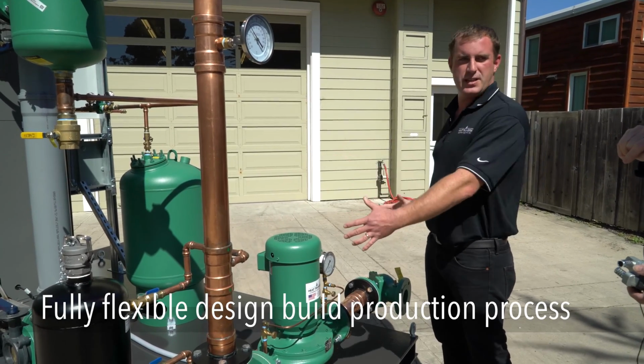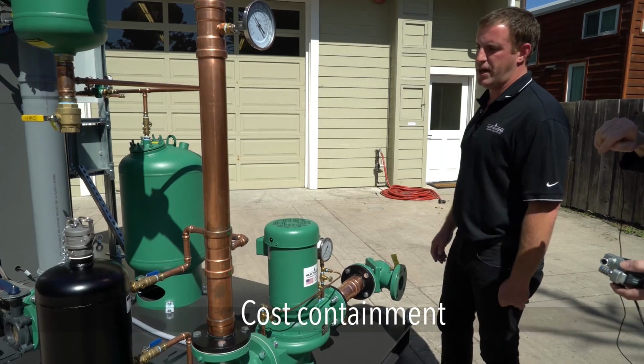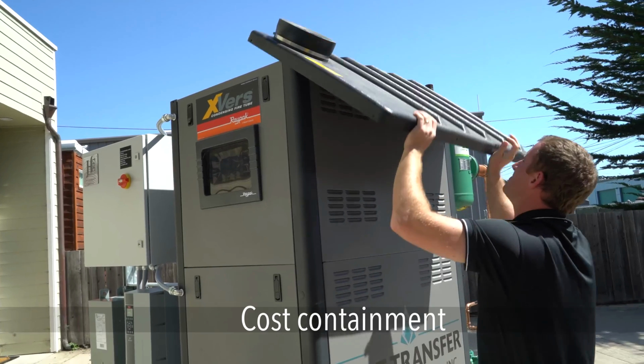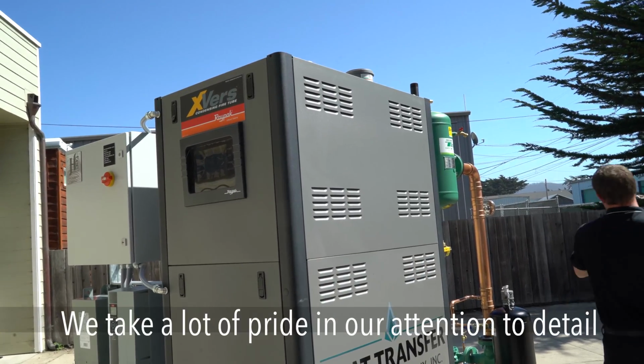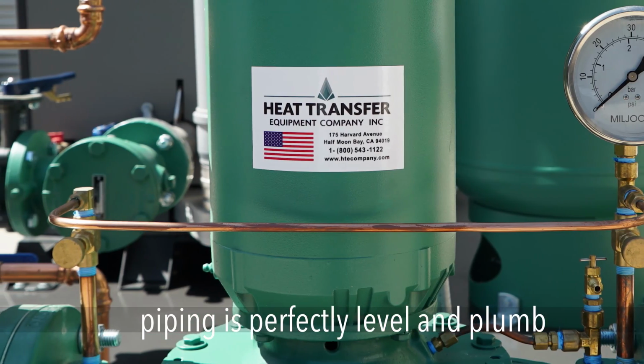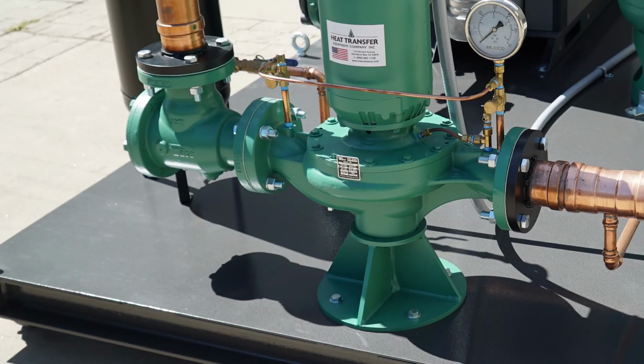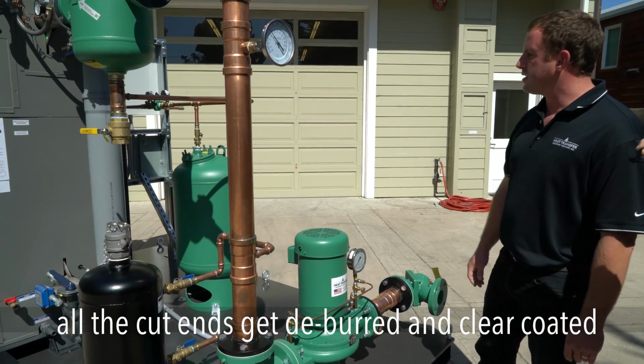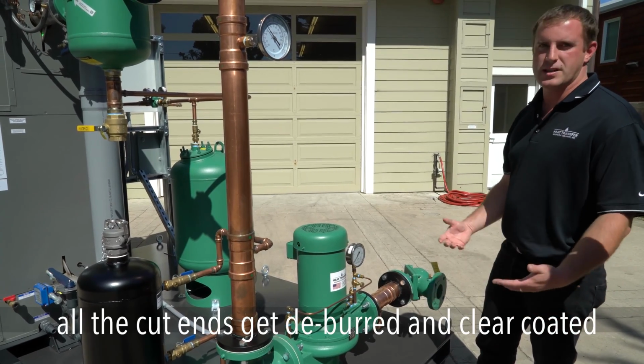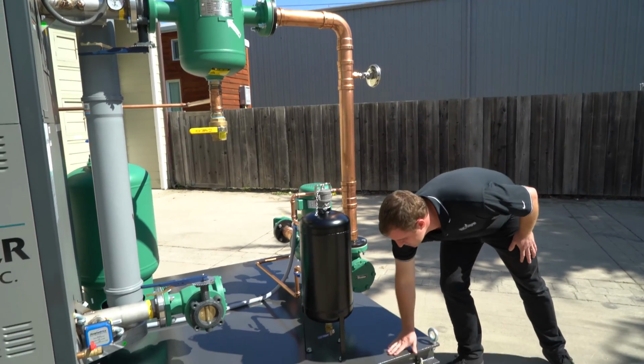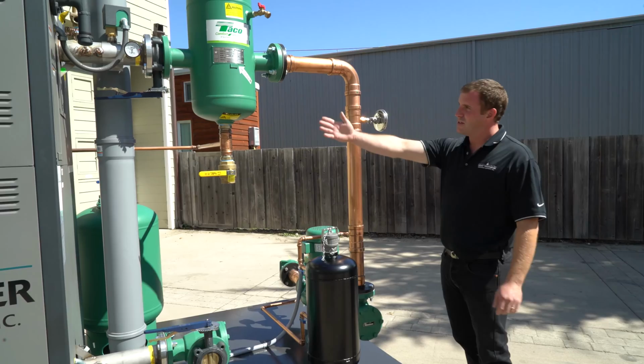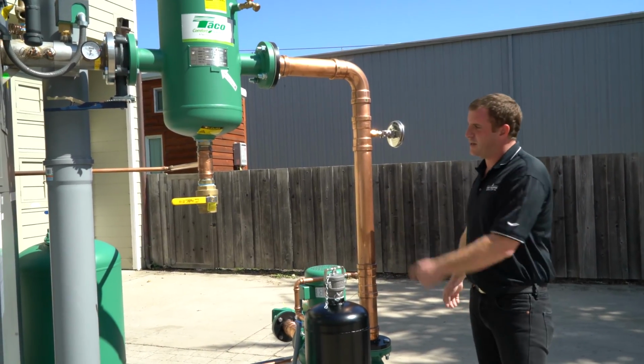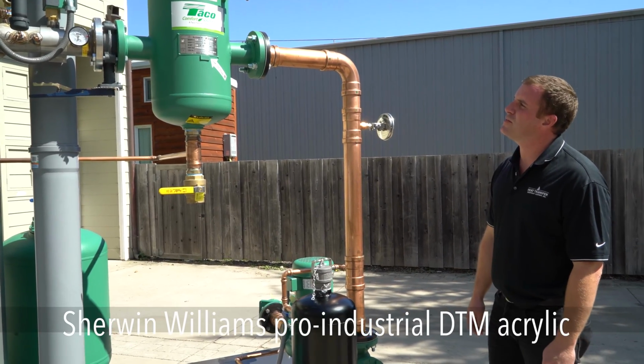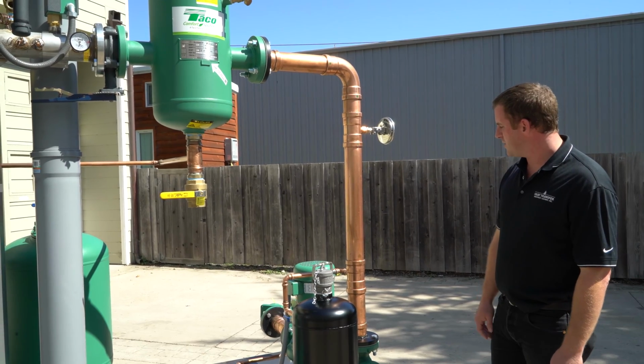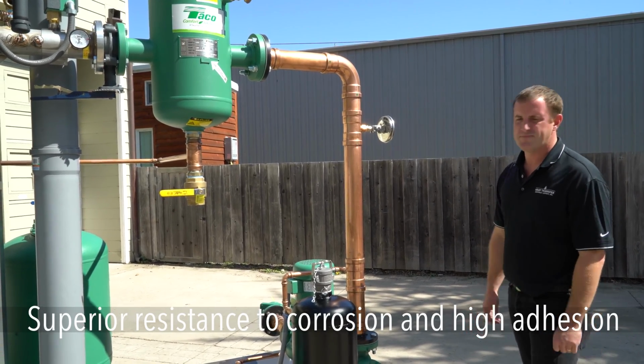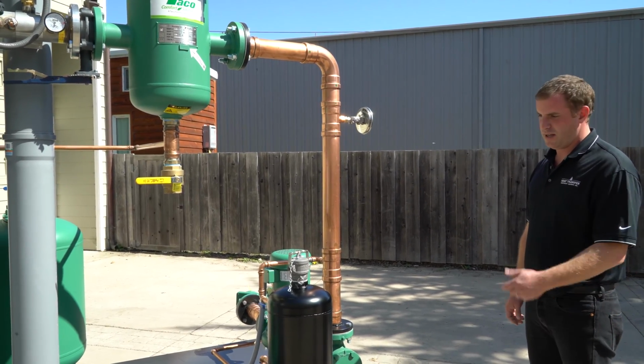Allocating enough space to service each piece of equipment, making it as compact as possible. Obviously trying to pass on cost savings to the customer, using as little pipe and fittings as possible to try to keep costs down. We take a lot of pride in making sure all the piping is perfectly level and plumb. Our finishes, the coatings that we do in-house, the hammer tone, powder coat, our strut frames, all of our cut ends get deburred and clear coated because the cut ends will rust if you don't put some kind of coating on them. This is powder coated and the boiler is powder coated. All of the main components, the air dirt separator, suction diffuser, pump, and expansion tank have been coated in-house with Sherwin-Williams Pro Industrial DTM acrylic, which is used because of its superior resistance to corrosion and high adhesion. We've had these things on roofs for 2-3 years and they look pretty much brand new.